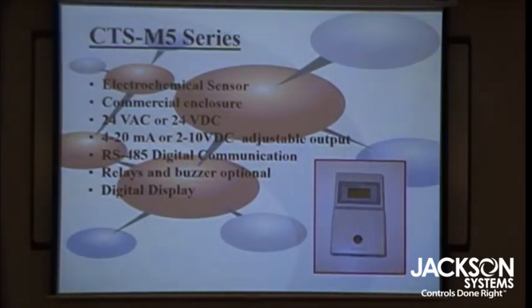Question. What's the range, adjustable range? Oh, the adjustable range, it's 0 to 250. But what you can do is you can adjust the 4 to 20 milliamps to whatever you want in that span. So let's say you wanted your 4 milliamps to read 20 ppm and your 20 milliamps to read 100 ppm, you could do that. Or let's say you wanted just 0 to 50, you can make your 20 milliamps 50 ppm. The display will still be the same, but your 4 to 20 changes. So whatever range you need. It is linear over the whole range, so we're able to do that.